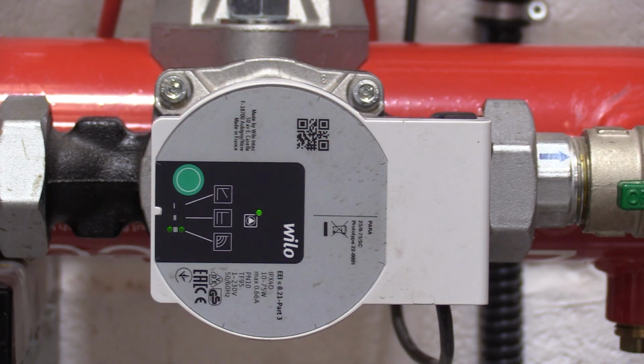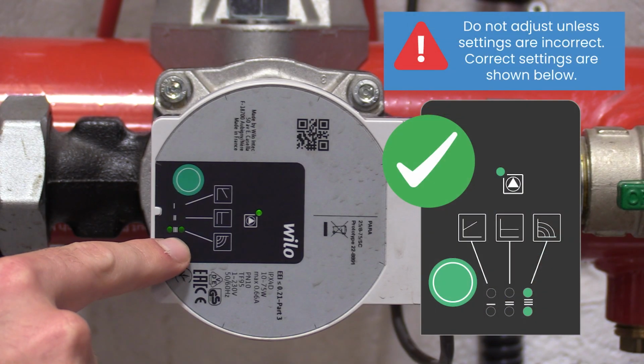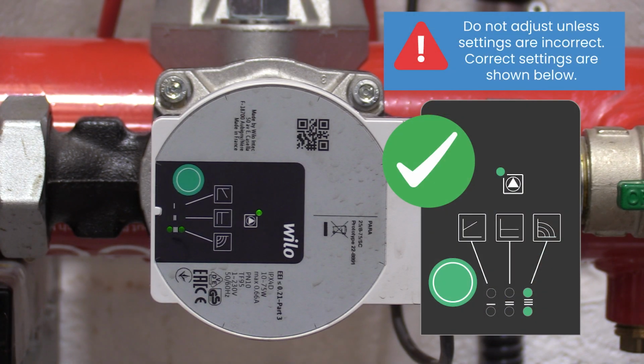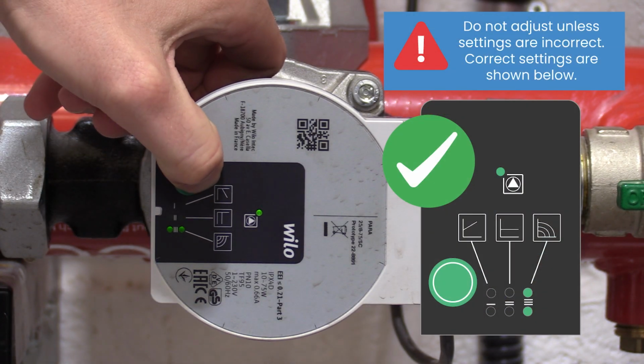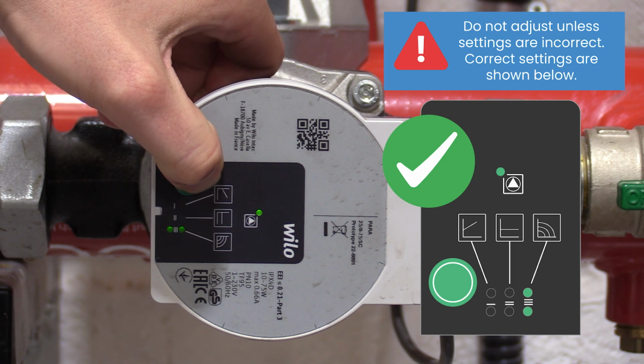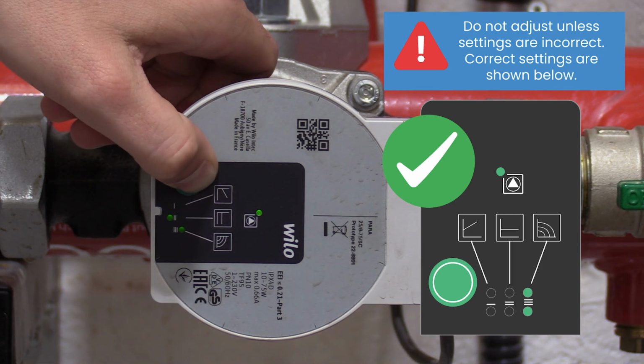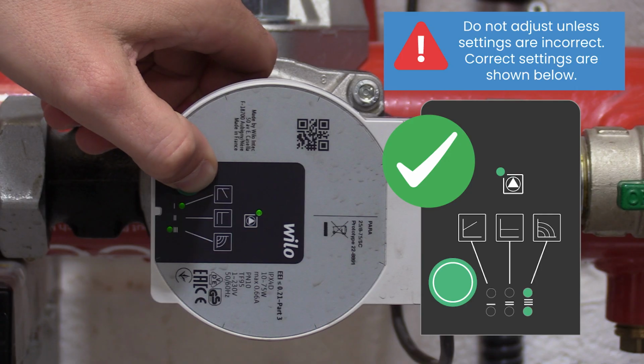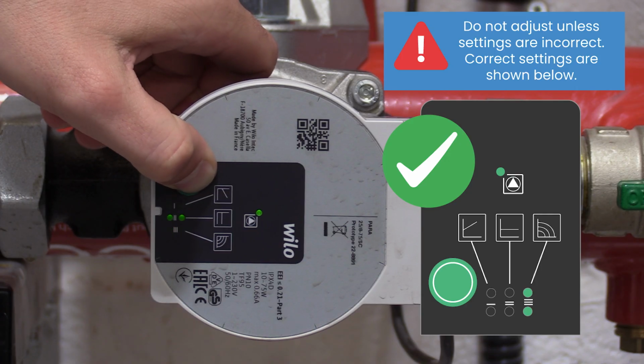The pump supplied with the Zonecheck comes locked to the correct settings. However, this can be checked. When the pump is running, the far right icons should be illuminated. If this is incorrect, hold the green pump button down for up to 10 seconds to unlock the pump, and then press the button to scroll through the different options.